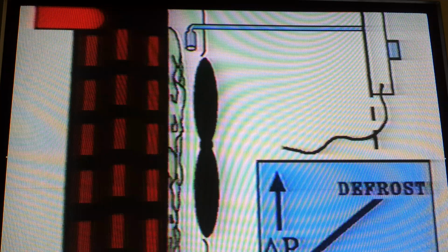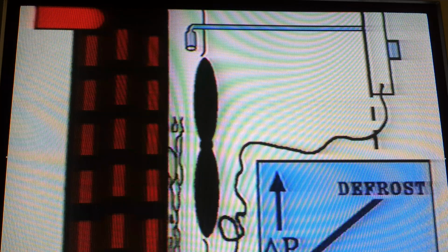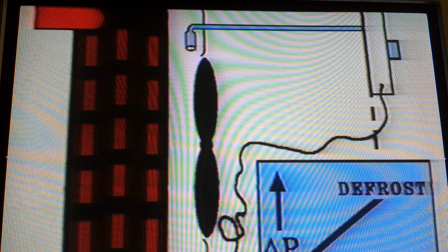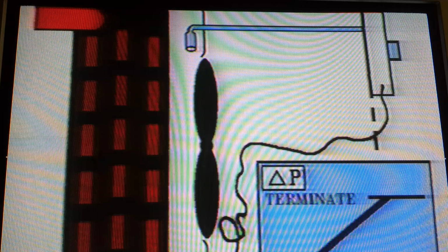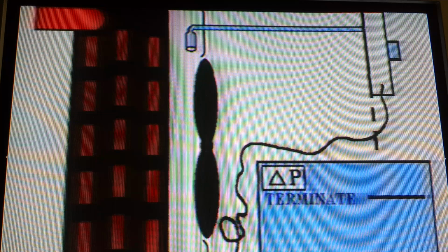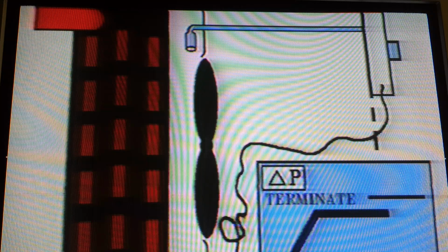Termination of the defrost cycle is most often done with a thermostat mounted to the liquid line. The defrost cycle is terminated when this location reaches the cutout point of the thermostat, normally about 65 degrees. This method of termination is universally used in all defrost controls. Many defrost controls also have a built-in time override in case the control does not terminate on temperature. Upon termination, the defrost relay coil is de-energized and the heat pump returns to its heating mode.